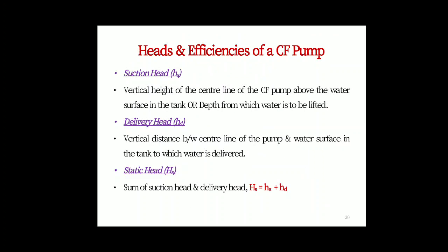Now let us see the different heads and efficiencies of a centrifugal pump. The first one is called the suction head: vertical height of the central line of the centrifugal pump above the water surface in the tank or depth from which water is to be lifted. Then delivery head: vertical distance between centerline of the pump and the water surface in the tank to which water is delivered. Then static head, HS: sum of suction head and delivery head constitutes this static head.